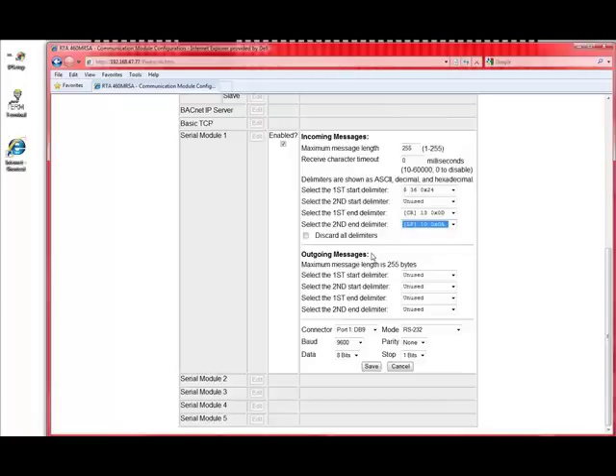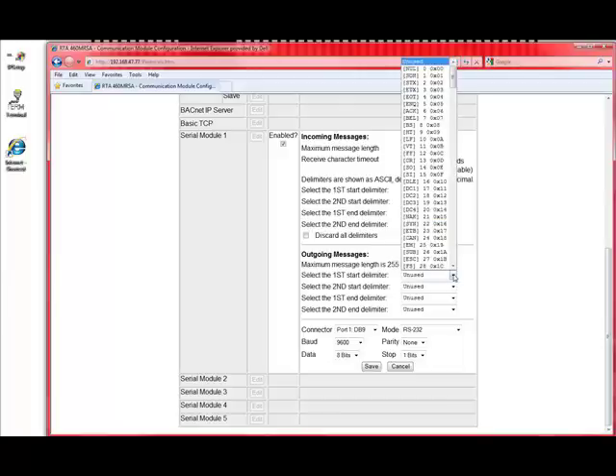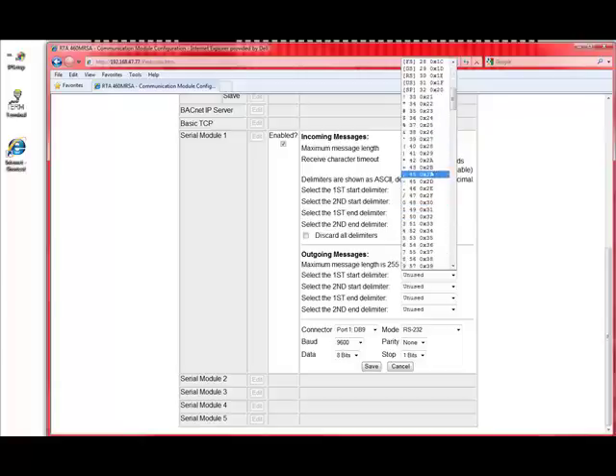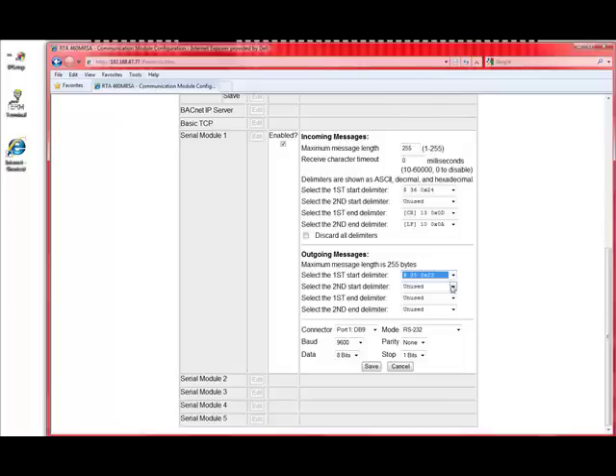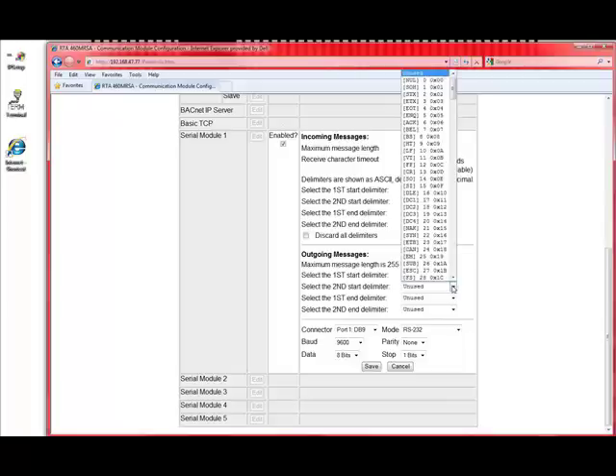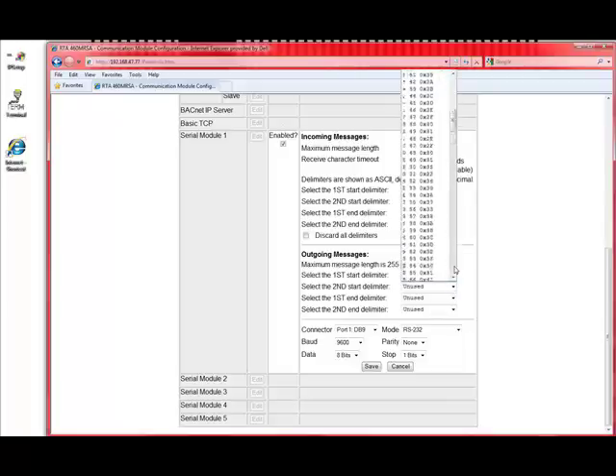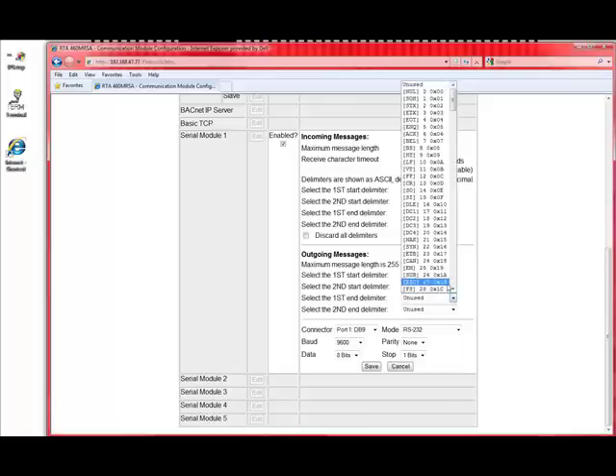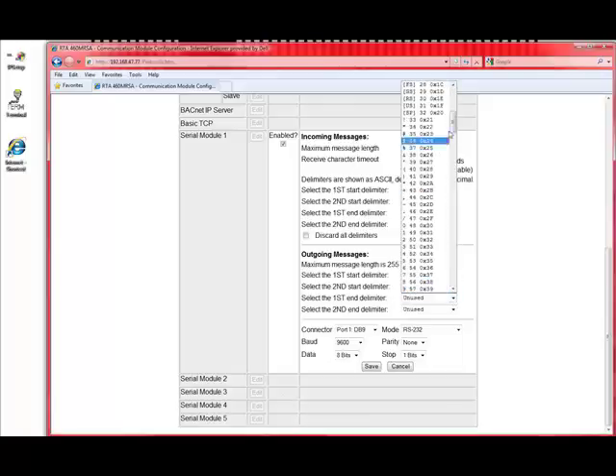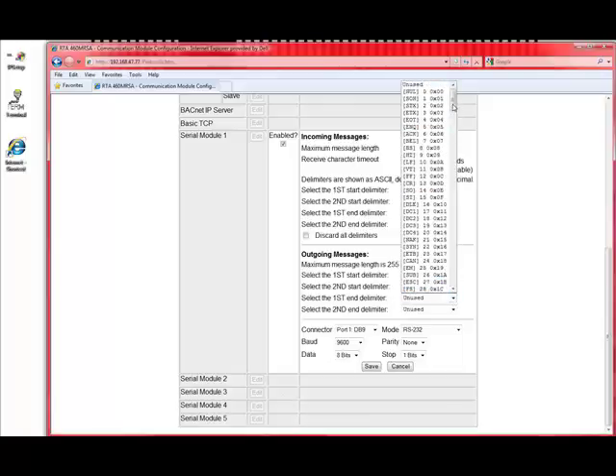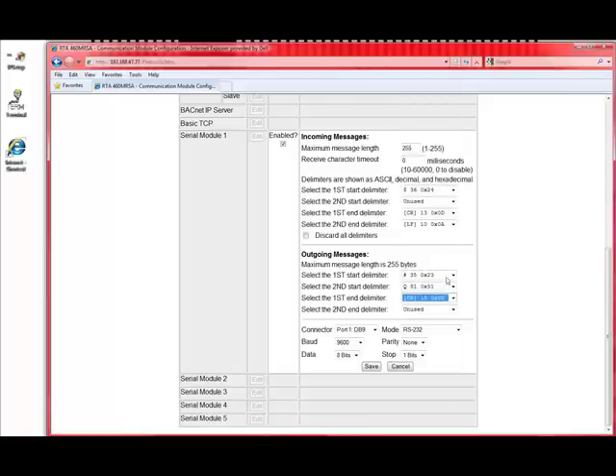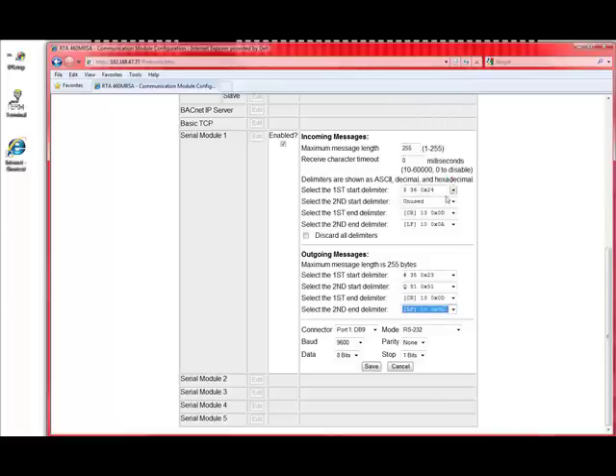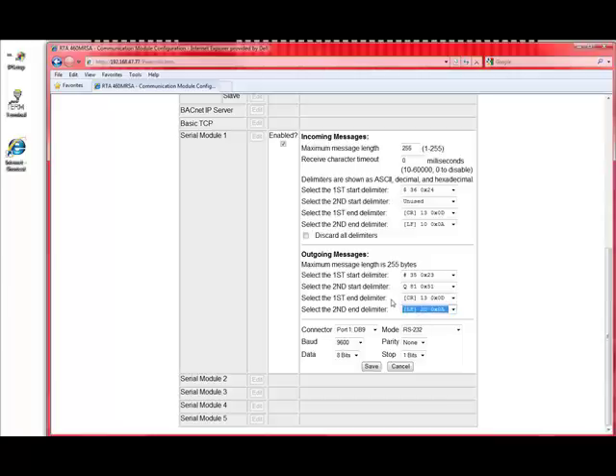Now, when we send messages, when we get data from Modbus RTU, we want to send it out, we have to pick the same kind of stuff. We're going to say, we want the module to encode, instead of a dollar sign this time, we want the module to encode a pound sign on messages going out. In fact, we're going to have it set up a pound sign and a Q on the message going out, and then we're going to also end it with a carriage return and a line feed. So, if we got in the characters ABC from Modbus RTU, we would attach a pound sign, we would send a pound sign, a Q, the ABC, then the carriage return, then the line feed. So, that's how you use the outgoing messages.